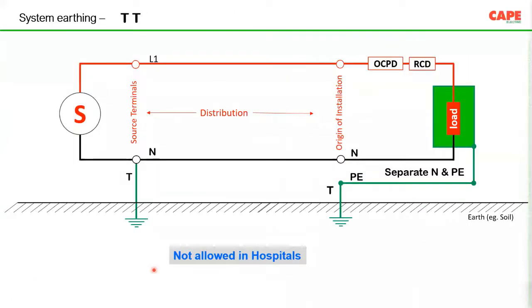It also means our general concept: what I am showing you is a source. Imagine it is a transformer or a DG. Neutral is connected to an earth electrode in soil. And then you have your electrical installation. Imagine some kind of load, a biomedical equipment which is connected to the power supply. The equipment vendor is asking, I need a separate earth. As a result, what people do is connect the body of the biomedical equipment to a separate earth electrode. Actually, this is not allowed in hospitals.